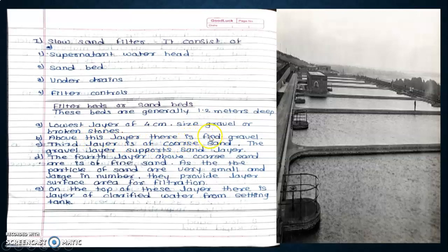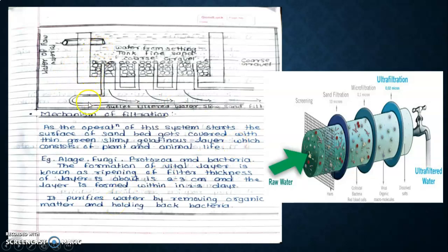Above this layer, there is fine gravel. The third layer is coarse sand. The gravel layer supports the sand layer. The fourth layer above coarse sand is of fine sand. As the particles of sand are very small and large in number, they provide large surface for filtration. On top of this layer, there is a layer of clarified water from the settling tank.